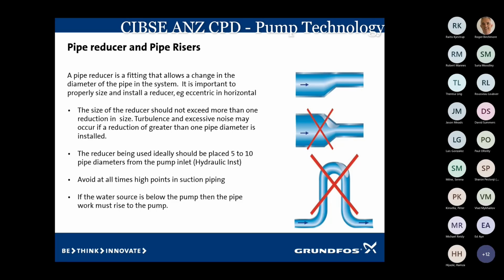Another one was at a hospital, and it had a number of water supply tanks, and it had a 300 mil line running off the tanks across the ground. They'd put a nib wall around the tanks, so they had a big hook like that over the top of the nib wall, and away it went. And that would accumulate air sitting in the top of that point there, and the pumps were starving. And once we cracked it and got the air out, then we understood that's where the problem was. Because you're always going to have air in the water. We can't do anything about it. If we change the temperature or change the pressure, that entrained air will come out.